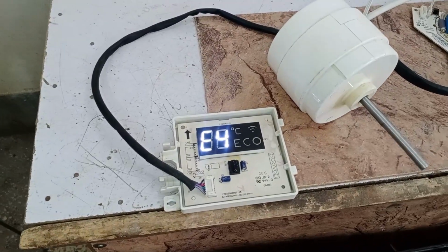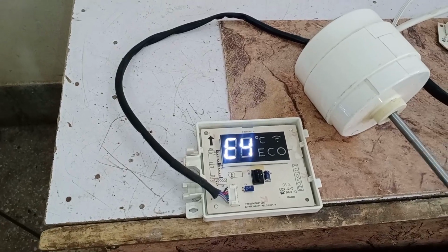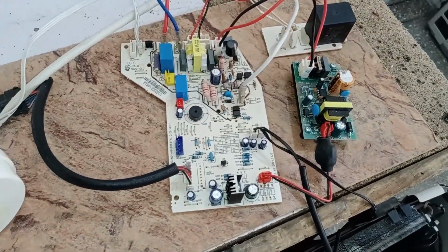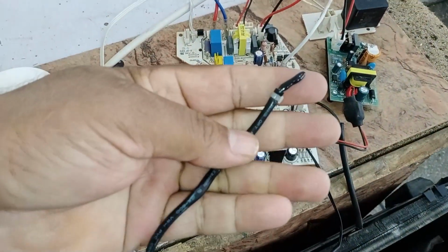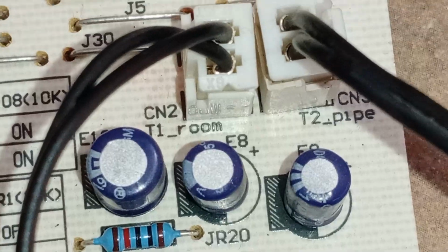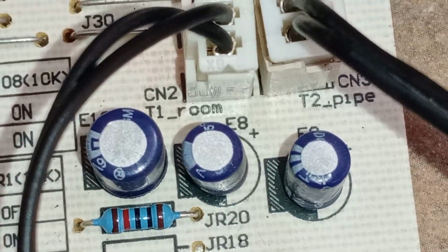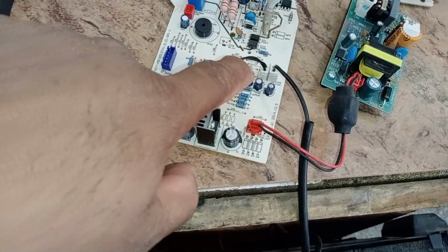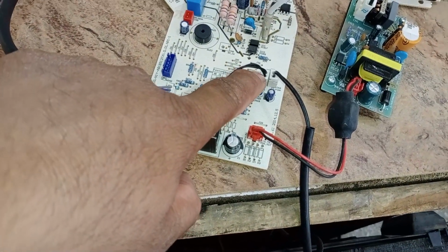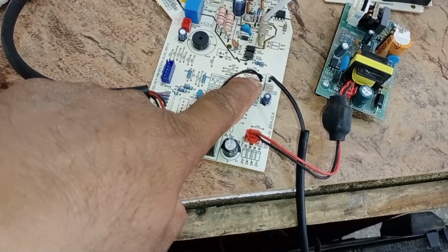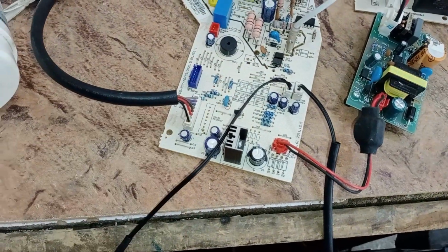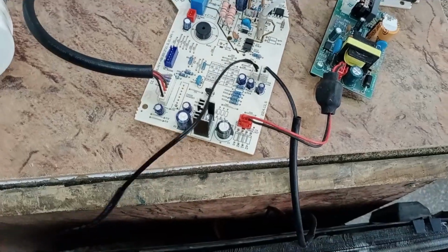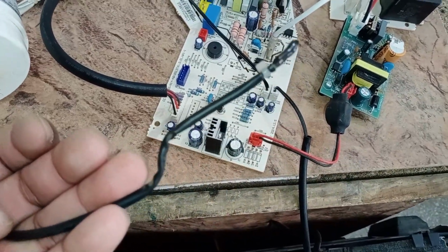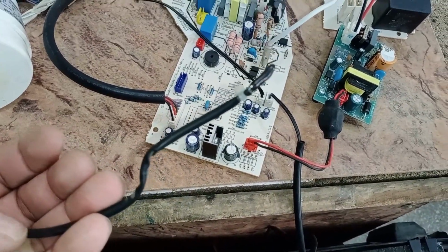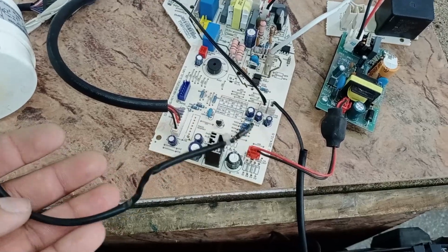Let me show you where the room temperature sensor is located on this unit. The room temperature sensor is located on the PCB here. This is the room temperature sensor, and it's connected to CN2. If there's a short circuit here, it will cause this problem. Also, if there's no 5 volts supplied to this point for some reason, it will also cause this issue. So you'll need to check the PCB in that case. However, the problem is usually with the sensor itself. If it's short-circuited, replacing it will resolve the E4 error and the unit will start working again.